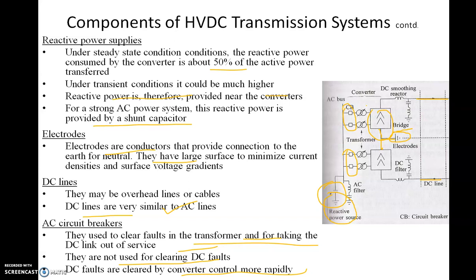DC faults are in fact more dangerous because they have a large and continuous current — there is no natural zero. Fortunately, we can control the DC fault current by controlling the firing angle of the bridge rapidly.